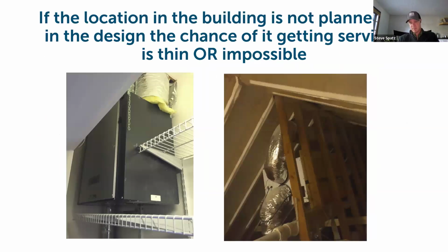And this is still happening and not uncommon to come across. This is a common one I've seen a lot, where you see an HRV or an ERV in the attic of a new build, and the only access to that piece of equipment is through a 16-inch square hatch in the bedroom closet that you have to take the shelving out to get to. ERVs and HRVs have cores in them, those heat recovery cores and filters that need to be cleaned and maintained a couple times a year in order for them to work.